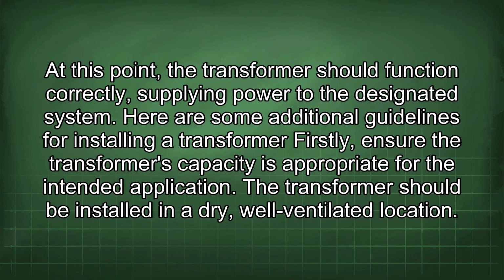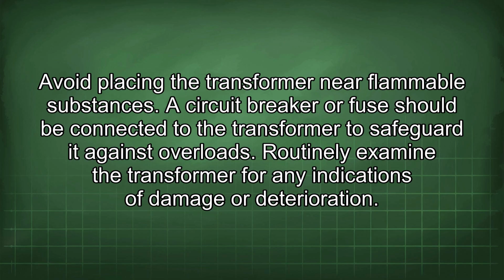Here are some additional guidelines for installing a transformer. Firstly, ensure the transformer's capacity is appropriate for the intended application. The transformer should be installed in a dry, well-ventilated location. Avoid placing the transformer near flammable substances. A circuit breaker or fuse should be connected to the transformer to safeguard it against overloads. Routinely examine the transformer for any indications of damage or deterioration.